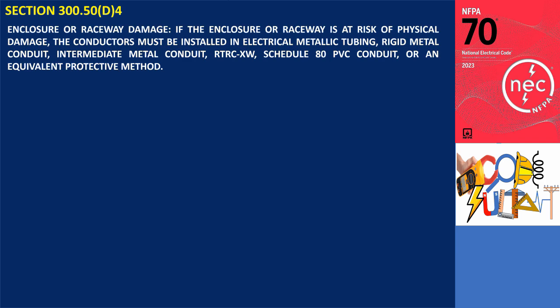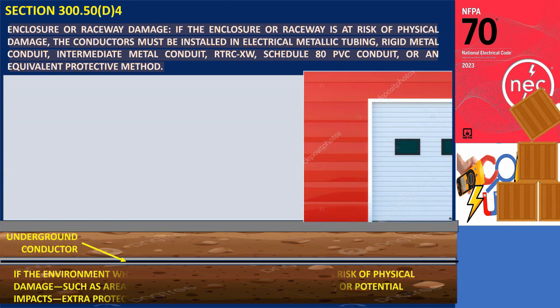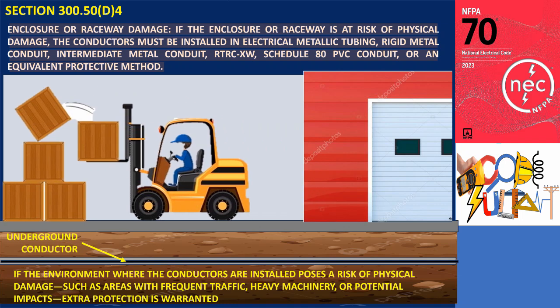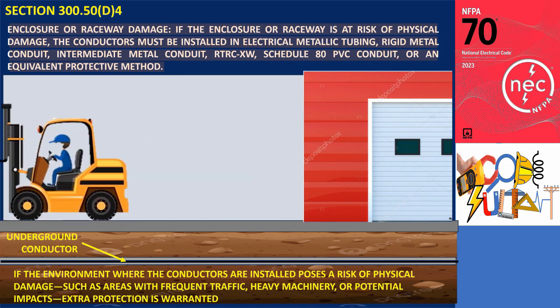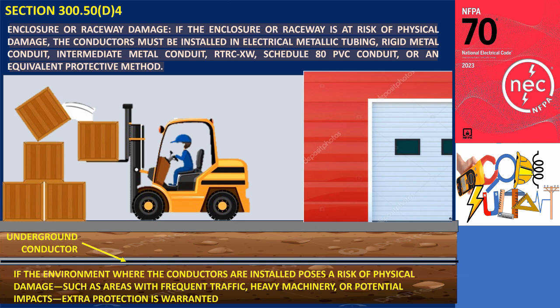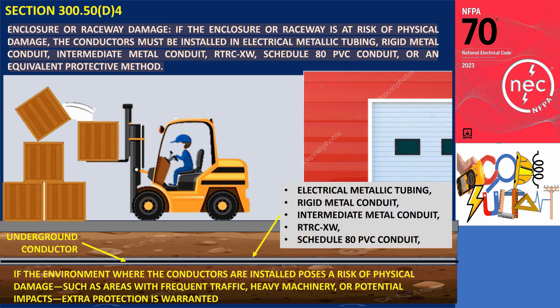Section 300.5(D.4), Enclosure or Raceway Damage: if the enclosure or raceway is at risk of physical damage, the conductors must be installed in electrical metallic tubing, rigid metal conduit, intermediate metal conduit, RTRC-XW, schedule 80 PVC conduit, or an equivalent protective method. If the environment where the conductors are installed poses a risk of physical damage — such as areas with frequent traffic, heavy machinery, or potential impacts — extra protection is warranted. Section 300.5(D.4) lists these acceptable protective methods: electrical metallic tubing, rigid metal conduit, intermediate metal conduit, RTRC-XW, schedule 80 PVC conduit, or an equivalent protective method.